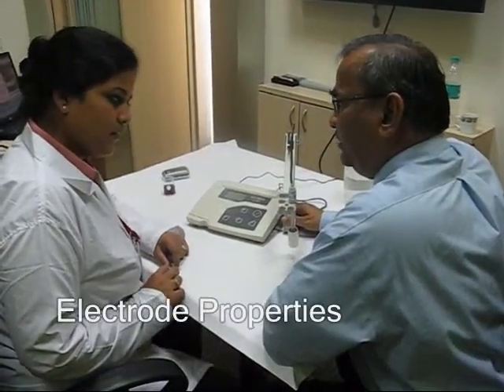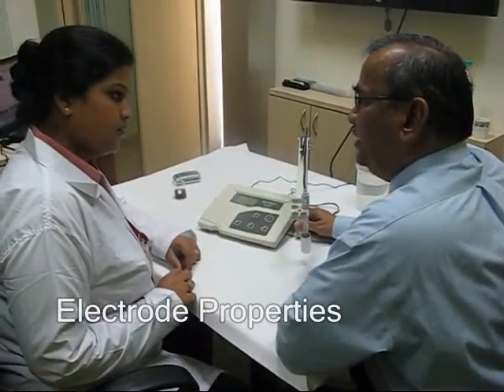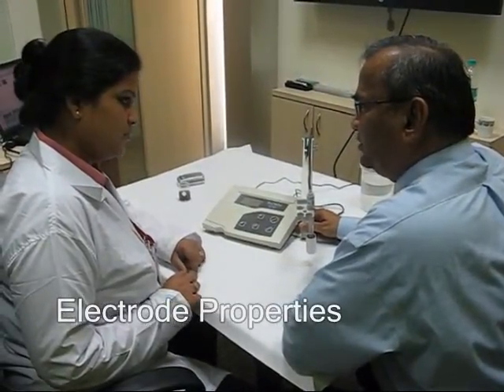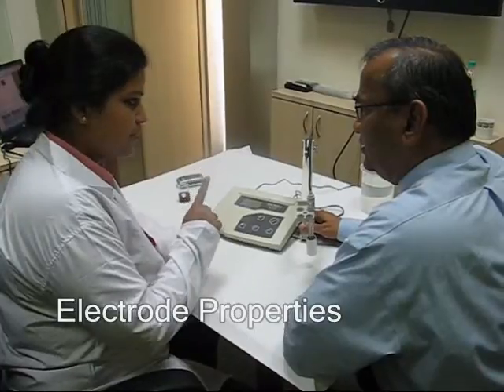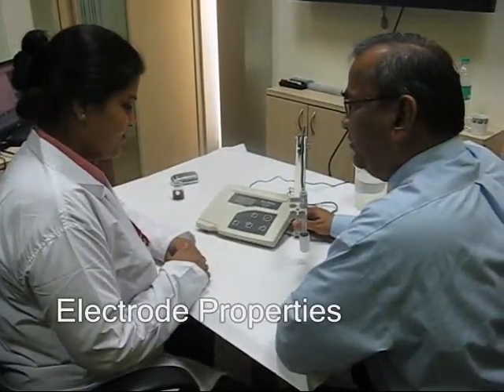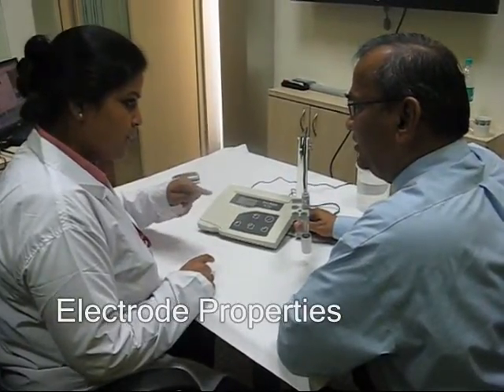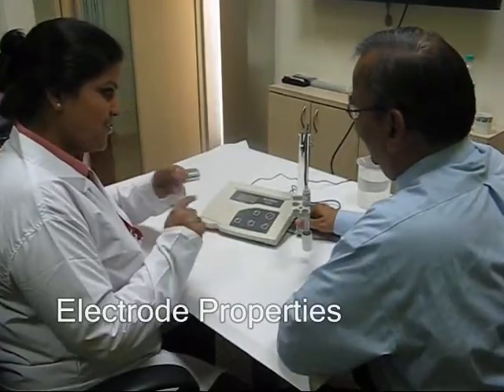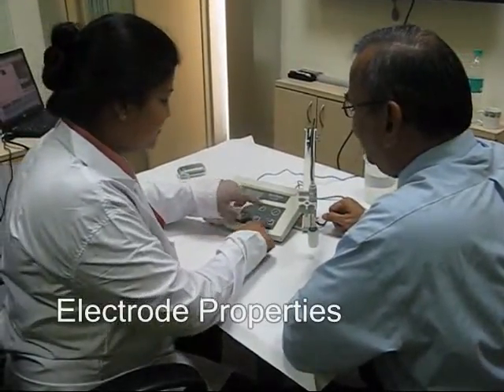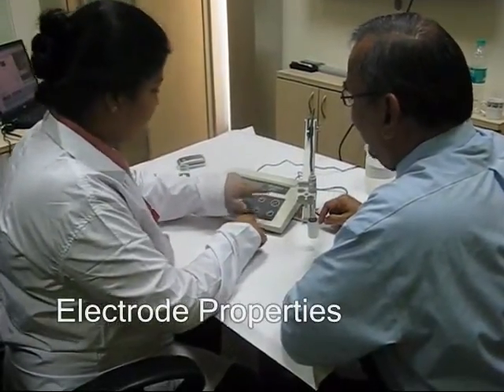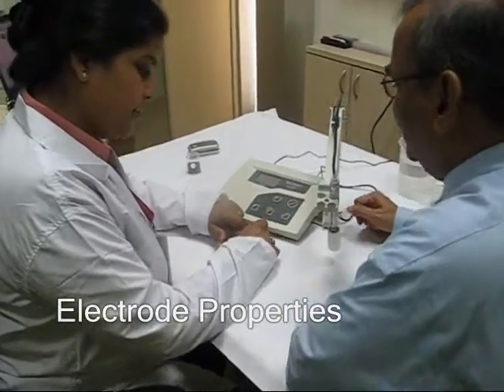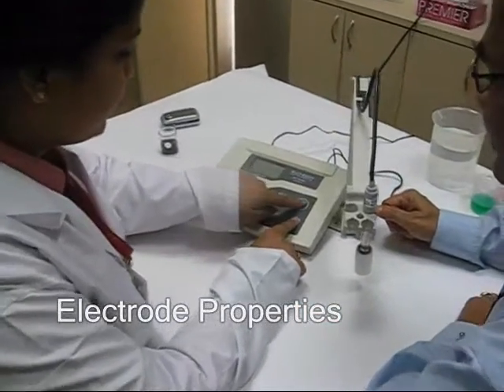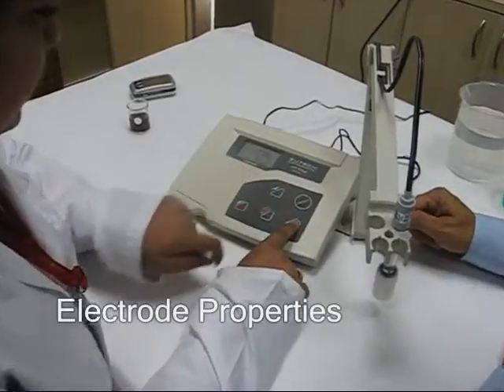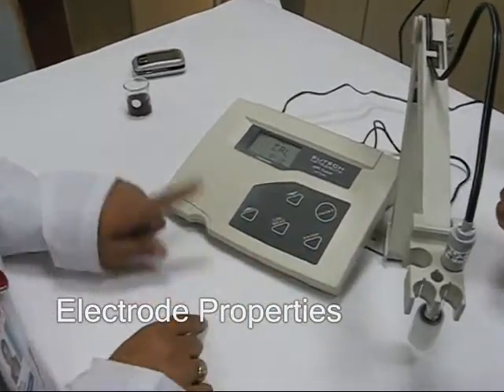Having completed the calibration, I want you to have a look at the condition of the electrode. How do we do this? Yes, I do remember. It is from setup menu. Excellent. But how do you get to the setup menu? By powering on the instrument with the enter key pressed. Excellent. Let's do that now. Yes. Let's switch the instrument off. And then now you have to get to the setup menu. Yes. Let's do that. Hold on. There you go. You're in the Setup menu.